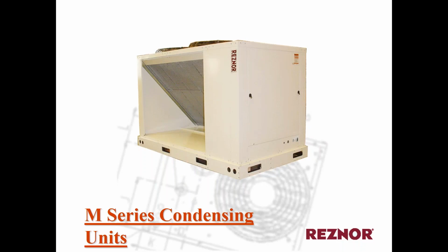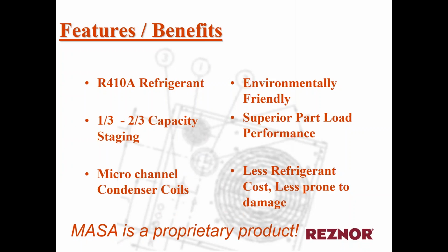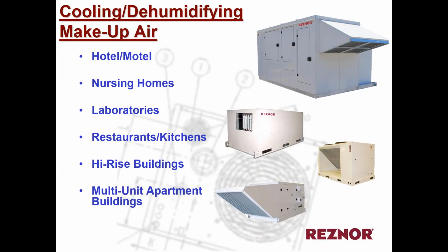We can also offer cooling coils, DX cooling coils and chilled water cooling coils in those indirect fired makeup air units that we talked about. And with the DX cooling units, we actually make a condensing unit called the M series, the MASA, which can be used for 100% outside air, cooling that makeup air as well as heating it. And this condenser is by no means to compete with Carrier or Bryant product that you already have. It's designed specifically for outside air applications because it's staged in a 1/3, 2/3 capacity, where as the outdoor air conditions change, almost on an hourly basis in our area, we can match the load with our capacity on the cooling end. And we make these units from 5 up to 20 tons.